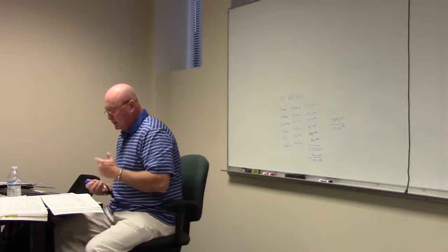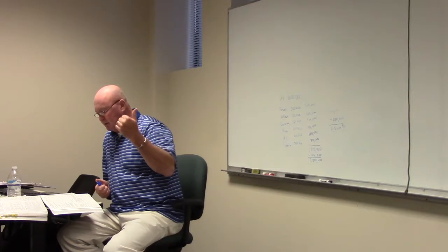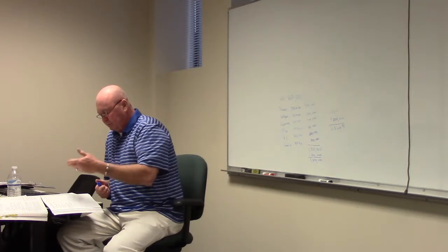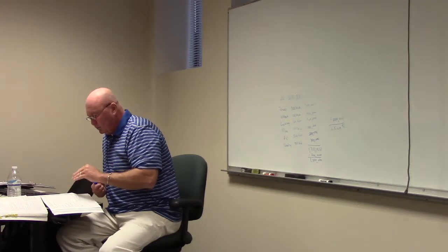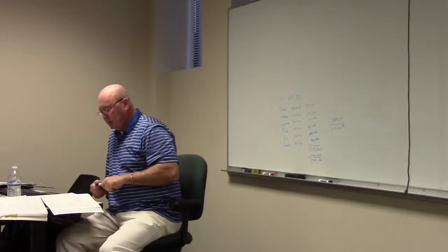So let's look in our book here. It says the combined load is 1.5, that's what we got. That includes the 200 air conditioning, which we did. The heating is larger. Based on 200,000 square foot of floor area, the load per square foot is 7.5. Now let's look. It says the demand factor for the portion of the load up to and including 3 VA per square foot is 100%.